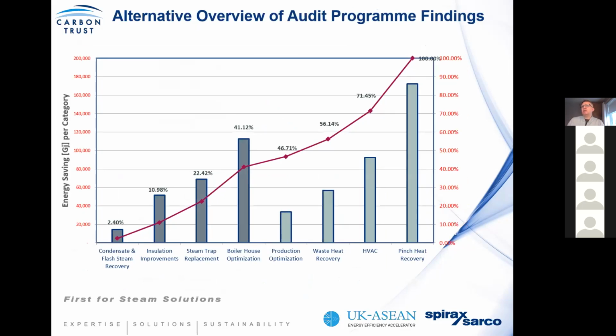Again, let's simplify it a bit further. We look at the 4 core areas of the steam fundamentals: condensate flash recovery, insulation, trapping, and boiler house optimization. And you need to understand where you are on your sustainability journey. So in other words, you shouldn't be looking to go to the complex engineering first. It was mentioned earlier about the low-hanging fruit or more easily addressable projects. So what you need to consider, where you are, is if these kinds of problems are those which could be addressed, seeing familiarity with your own site.